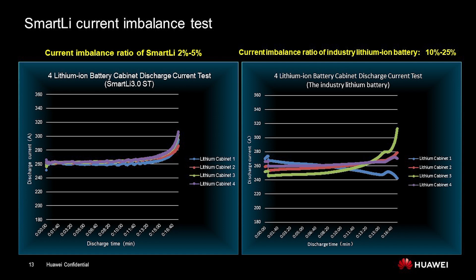It has several problems. The first one is that the imbalance current will cause overheating of the cables. Secondly, as the green curve shows, it may trigger the overcurrent protection. If one cabinet is overcurrent, the rest of the cabinets are overcurrent too, because the rest of the modules or cabinets can't support such higher temperature, higher current. So we need to keep the imbalance ratio lower. That is the principle of the intelligent battery management module. We control the current based on the state of health.